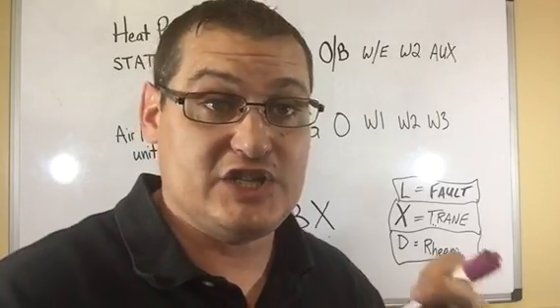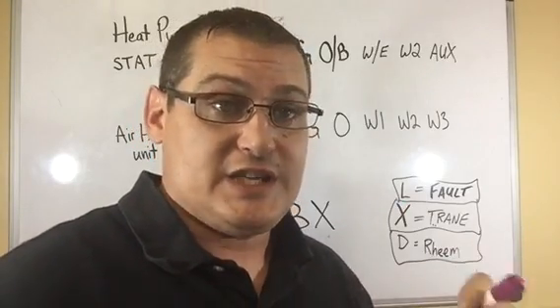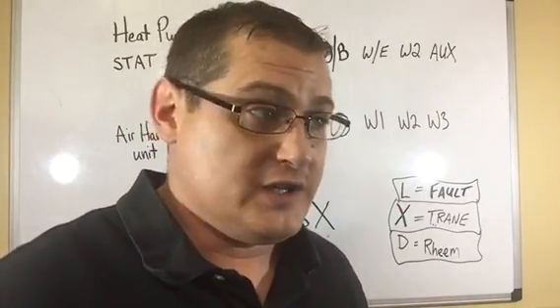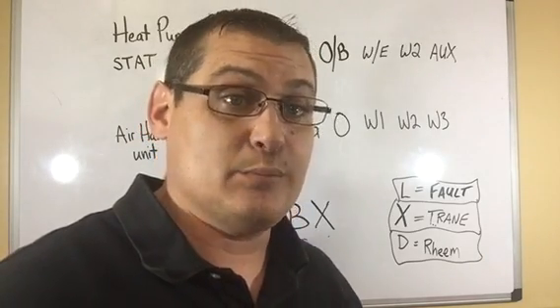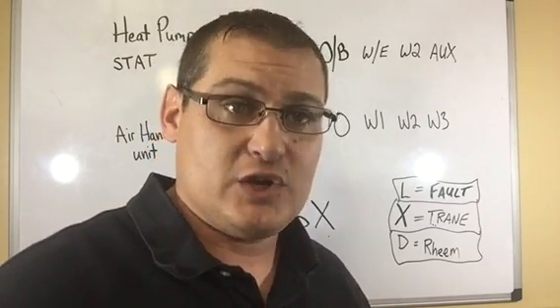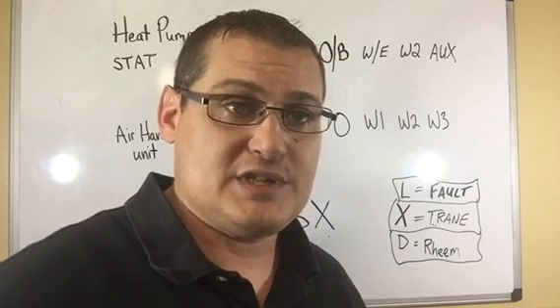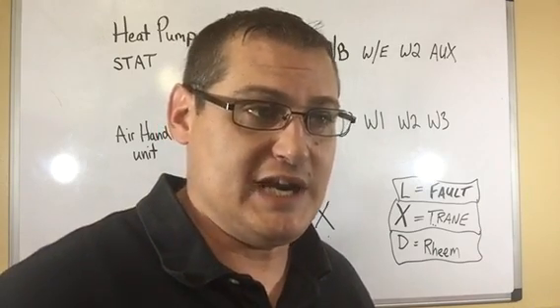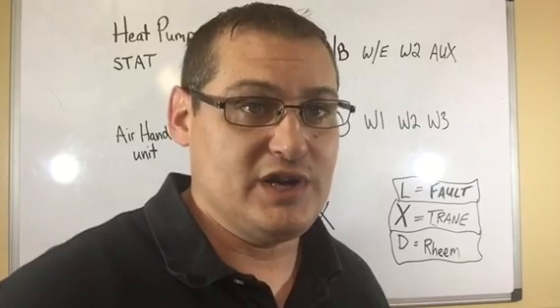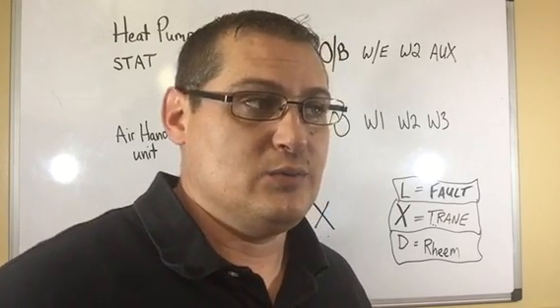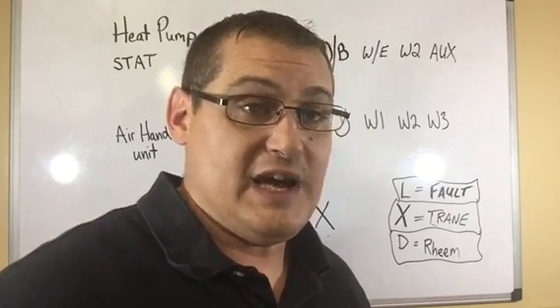Just like when we talked about basic thermostats, you've got a G terminal. G is for the fan, R is the 24 volts, Y is the compressor, which I called cooling earlier, but for heat pumps it powers the compressor outside. It's the signal to turn the compressor on. We'll just call it compressor. Then you've got W, which is call for heat.